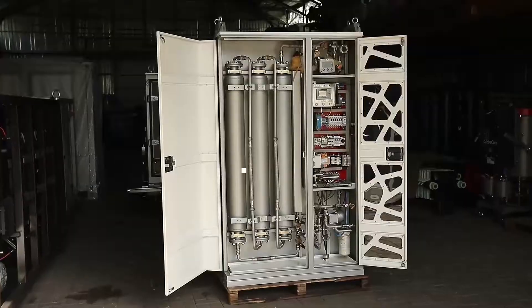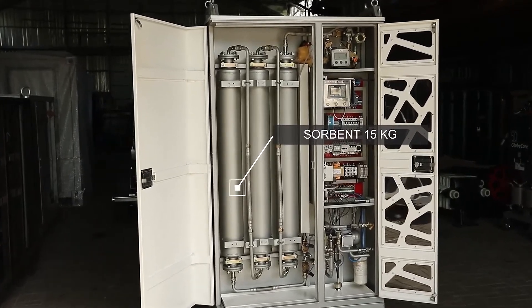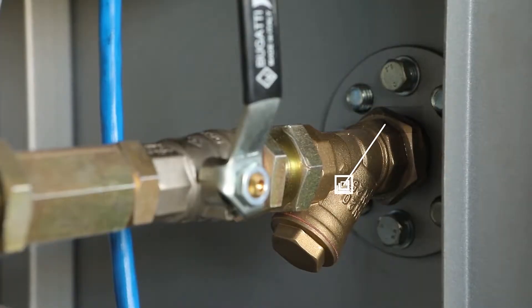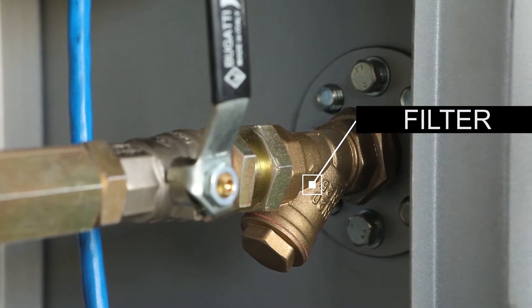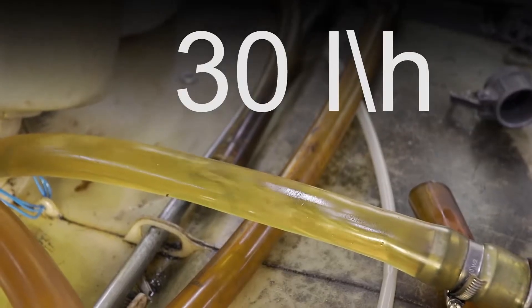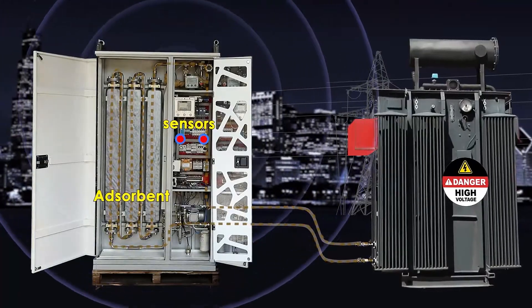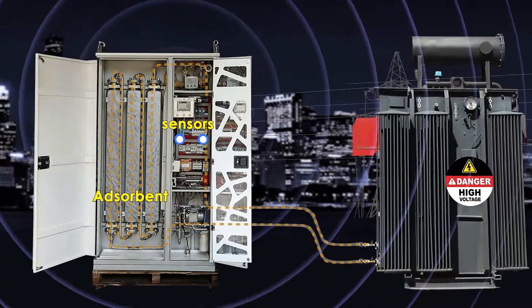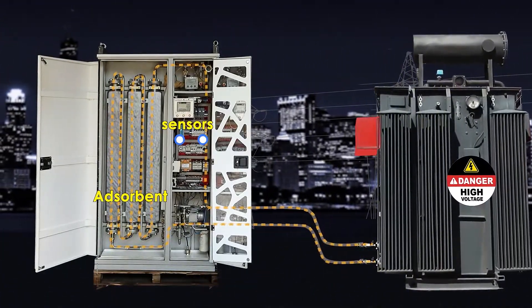The drying occurs by pumping the oil through three cartridges, each containing 15 kg of sorbent, while solid impurities are removed using a 10 micron filter. The flow rate is 30 liters per hour, and the oil is processed without shutting down the transformer, at any time of day, in any weather conditions, with or without the presence of service personnel.